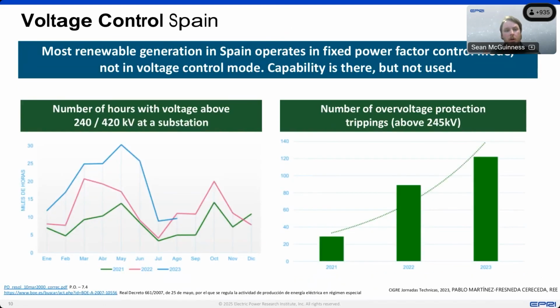Also in Spain, for voltage control, pretty much all of the wind and solar plants operate in fixed power factor control mode. So they're not actively controlling the voltage at their terminal. They're not necessarily sources of dynamic voltage support. The capability is there and it is required in the grid code, but it is not commonly used, although that may be changing.